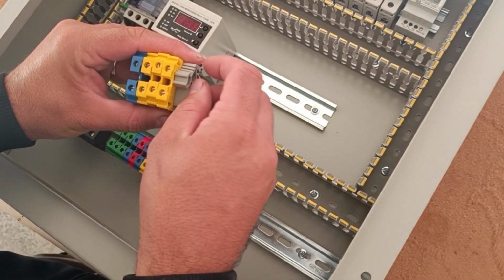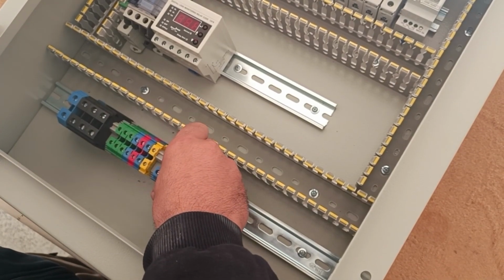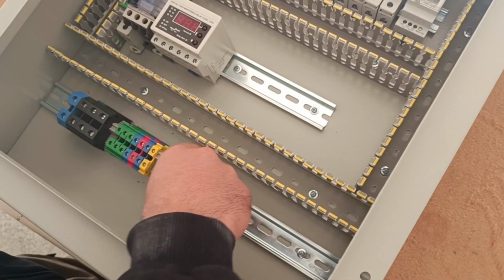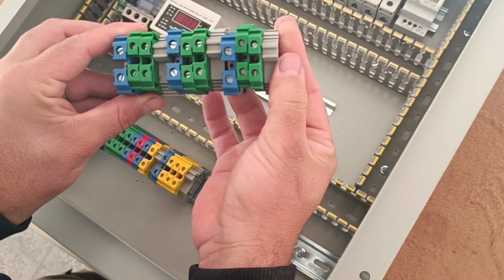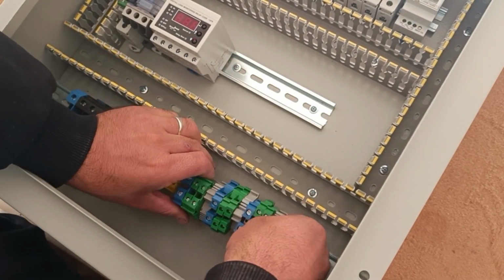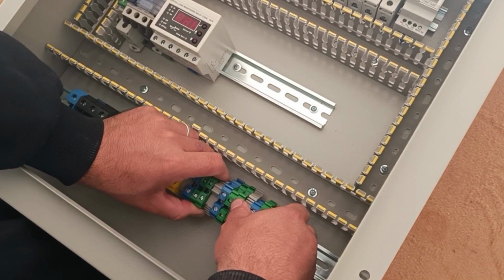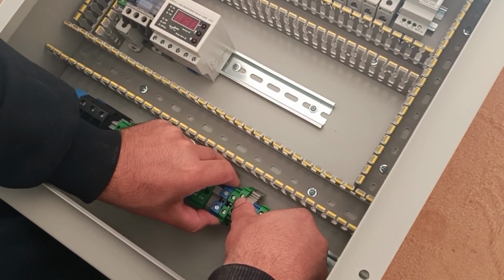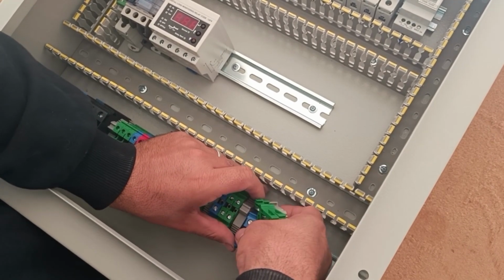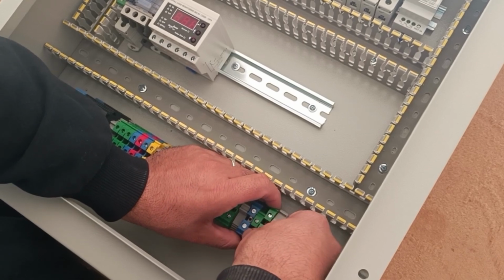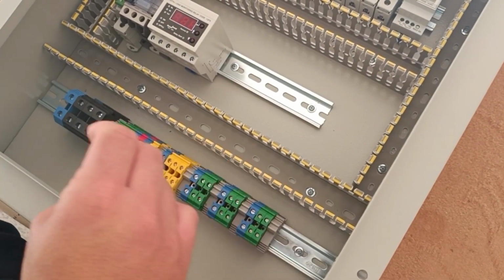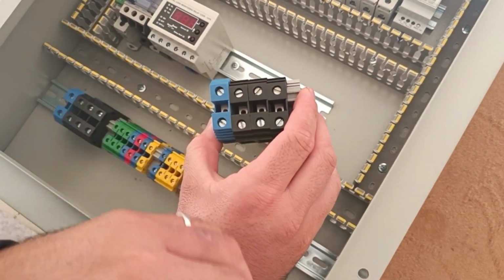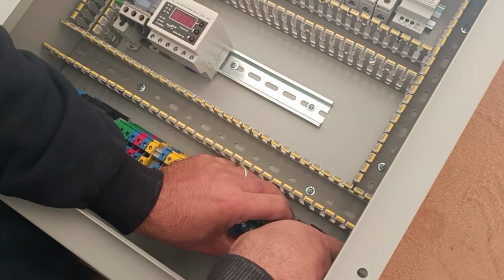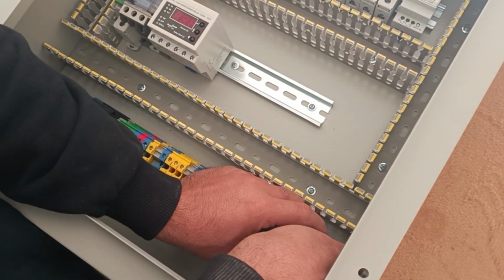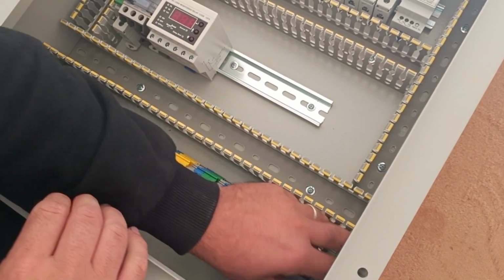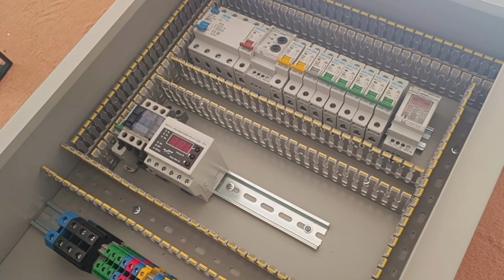The blue terminal is for the neutral. These terminals are for the single-phase output. And these are four additional terminals that provide three-phase electricity directly from the electrical panel. The installation of equipment is finished. Now we start the wiring.